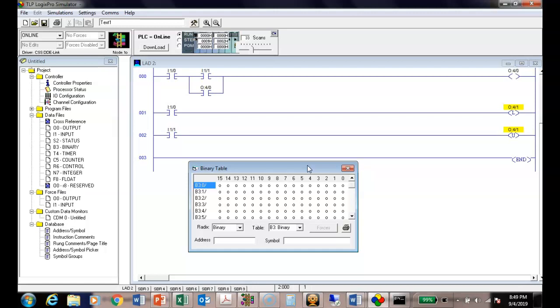These are coils that do not have to use an output. Their contacts do not go to the outside world. So I'm not going to use these to turn on a light. People don't understand that, and they think if they've got a relay, they've got to assign it to an output, right? But if what that relay controls doesn't require turning on something, then we can use what we call an internal coil. We use these for a lot of things.